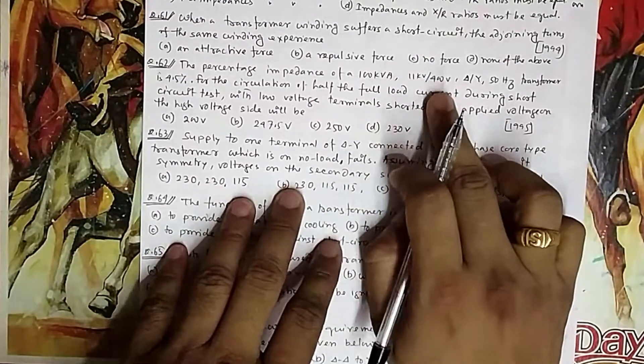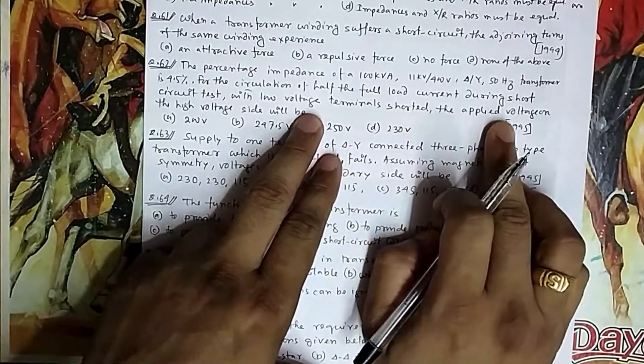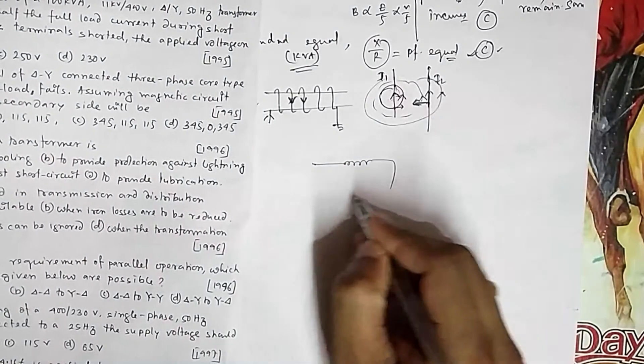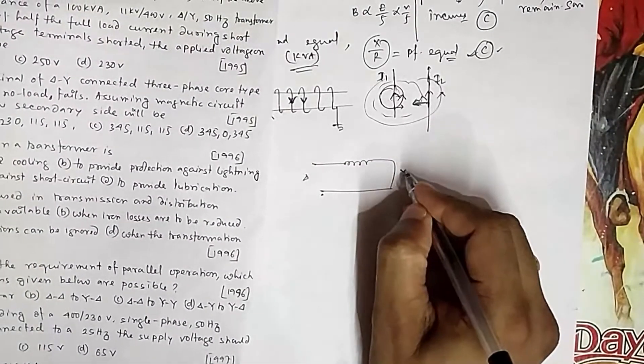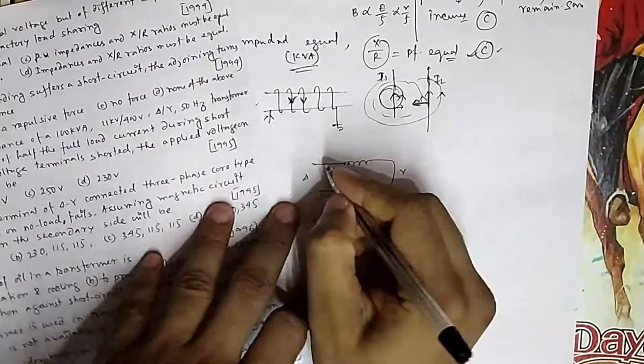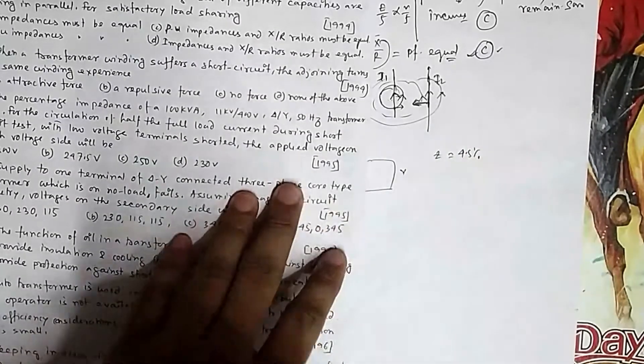Question 62: The percentage impedance of a 100 kVA, 11kV/400V, delta-star, 50 Hz transformer is 4.5%. For the circulation of half full-load current during the short circuit test with the low-voltage terminal shorted, we need to find the applied voltage on the high voltage side. The low voltage is star and high voltage is delta. Referring all windings to the delta (primary) side, Z equals 4.5%.